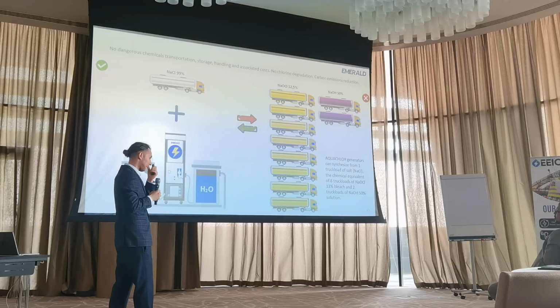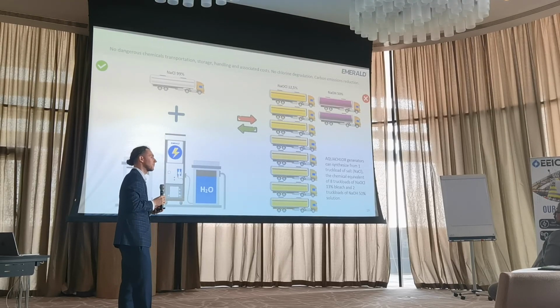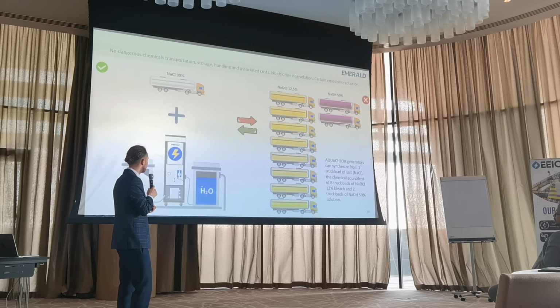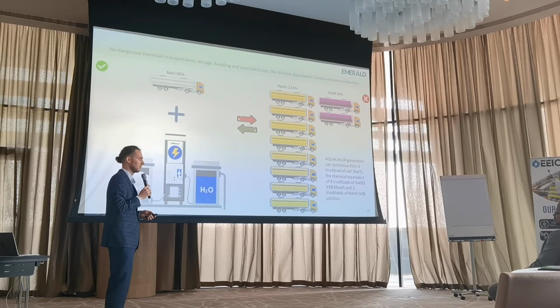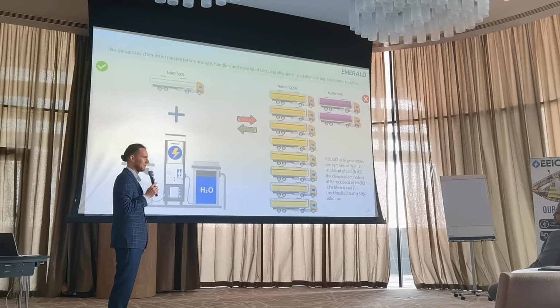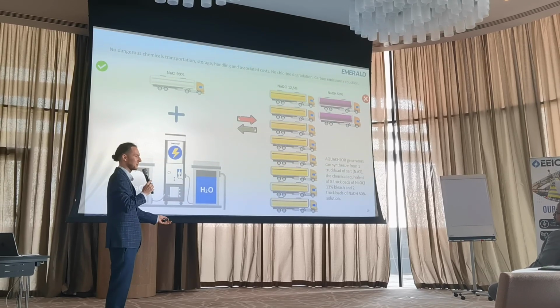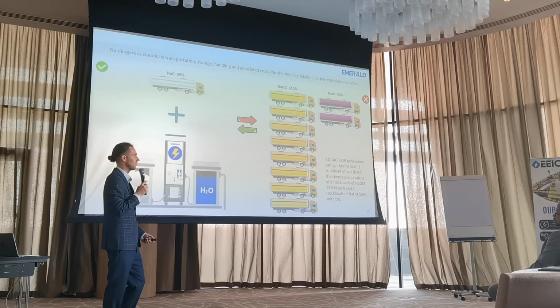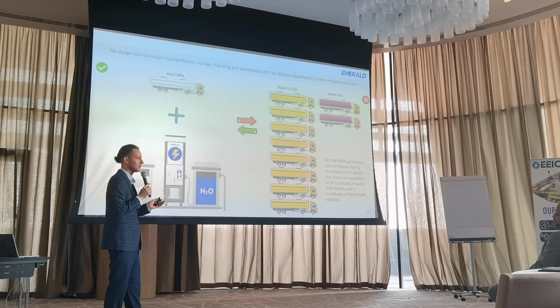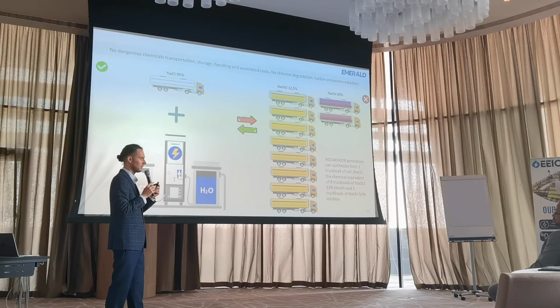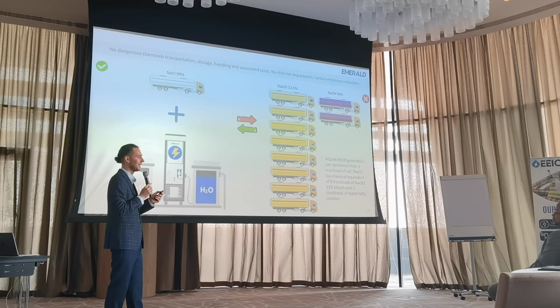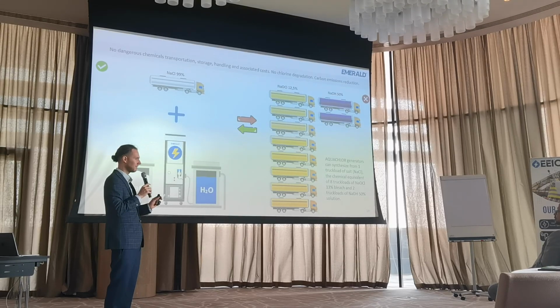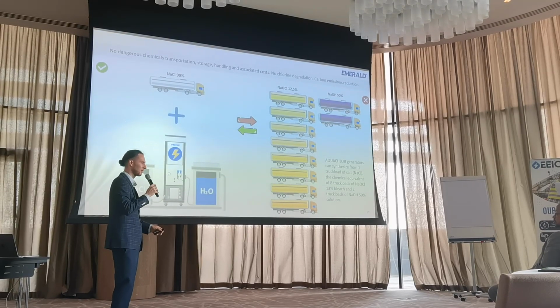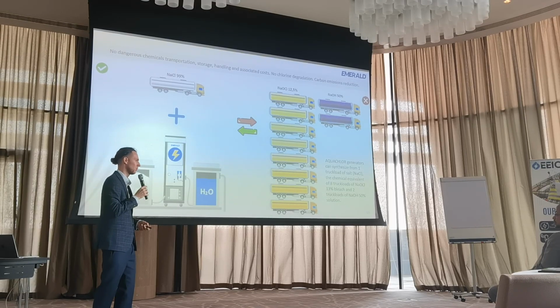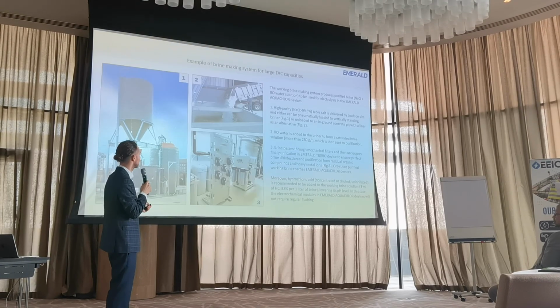For the water, how much do you need and how do you get pure water? It's reverse osmosis water. For desalination plants, they already have quite a lot of it, so we don't even need to install additional reverse osmosis systems. For other facilities, we install just a small reverse osmosis system. To produce 1 kg of effective chlorine, we consume only around 8 liters of water, a very small amount. For most projects, even a household reverse osmosis unit like the one under your kitchen sink would work. So it's a very small amount of reverse osmosis water needed.